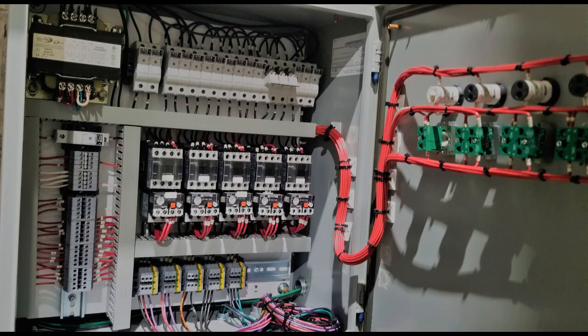Now I will show you the physical wiring of the transformer inside the control panel. Just a safety disclaimer, this transformer will be having live power right now, and only an authorized person should check or test it while it has power on it.